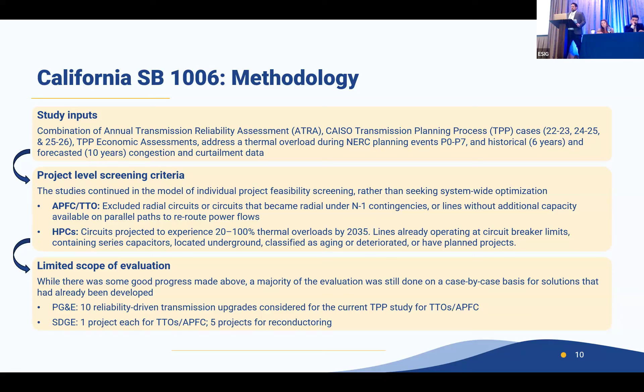For Southern California Edison, PG&E, and SDG&E, there were no transmission topology optimization or advanced power flow control opportunities identified. For dynamic line rating and high performance conductors, there were actually quite a few opportunities identified. There were 23 DLR lines identified for CAISO to do further evaluation on, and 62 potential high performance conductor candidates that were essentially screened as good candidates if future reliability or economic congestion issues arose. So those are the results.